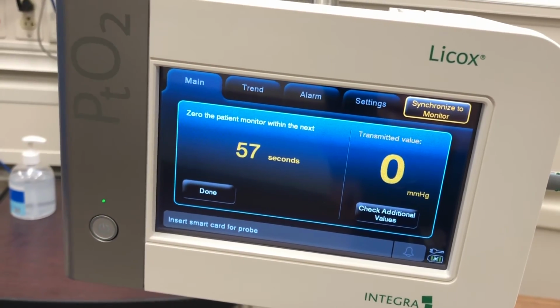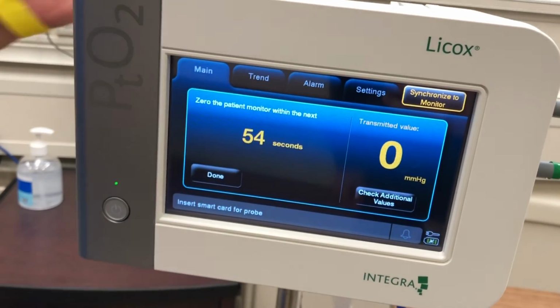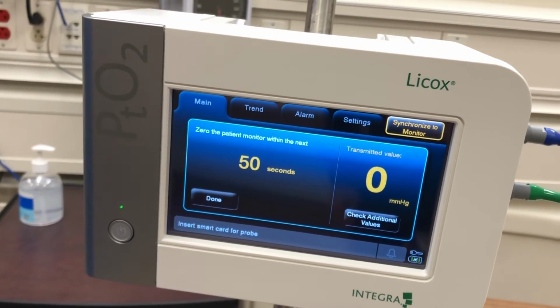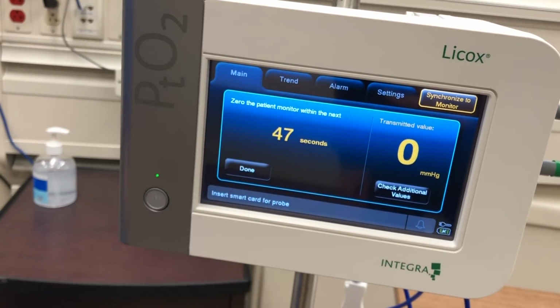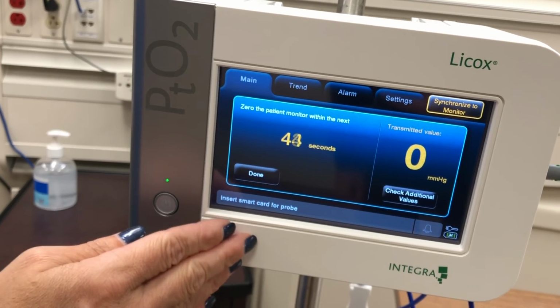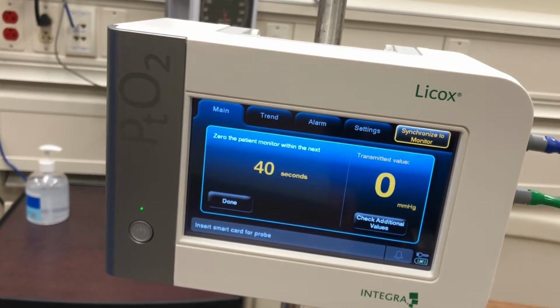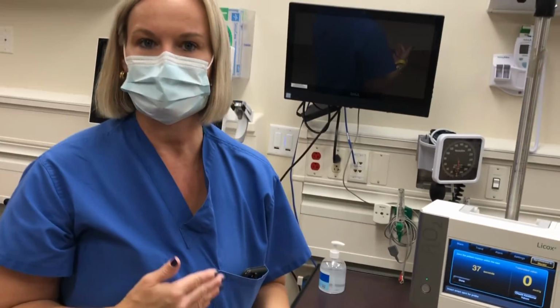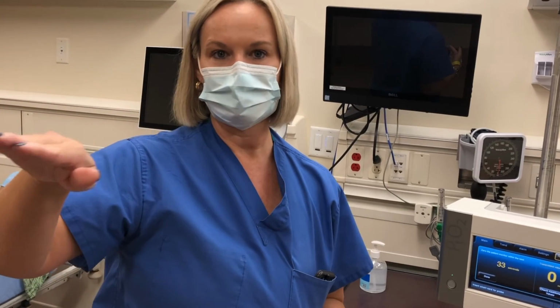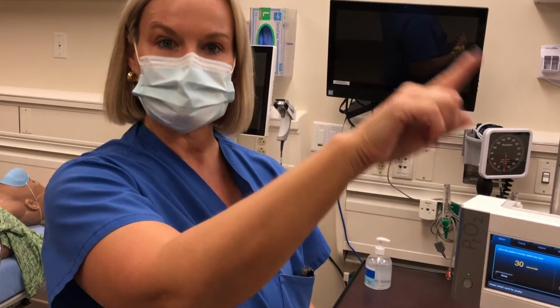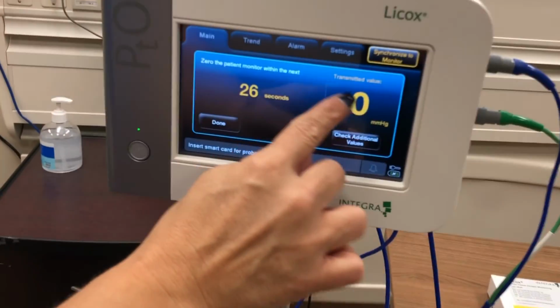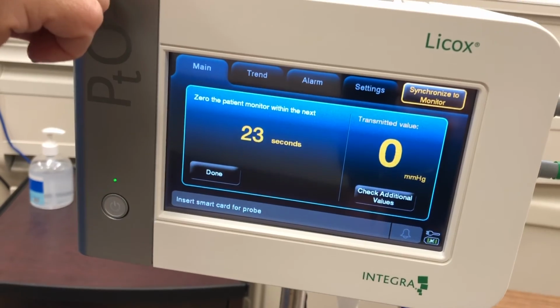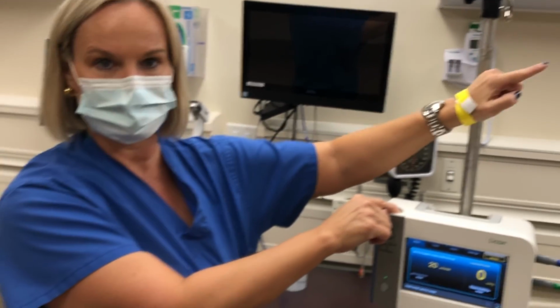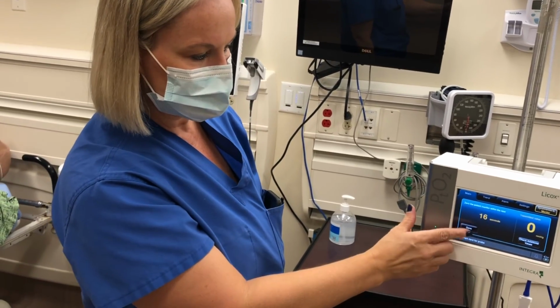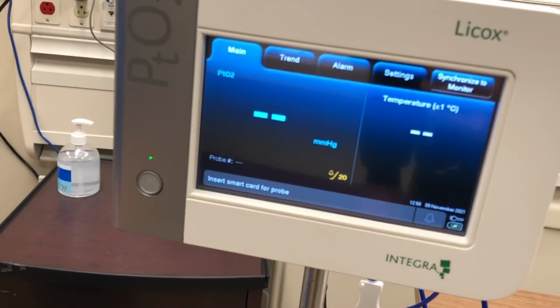And then synchronize to monitor. We're not going to do that for purposes of today's demonstration, but the easy thing to think about here is that you will have a cable that is connected to your GE monitor. You see that the clock is basically going down, and it's a 60-second clock. All you need to do is go up and hit 0 on your patient monitor, just like you would zero any other pressure line, for CVP, art line, ICP, whichever port you have put this in and labeled for Licox. You're going to go up and hit 0 on that. And what's happening, it literally tells you transmitted value. This is this monitor syncing to your monitor, sending a calibration of a 0 millimeters of mercury threshold. Once you've done that on the monitor, you hit done right there on the touch screen. And then you're back to your main screen.